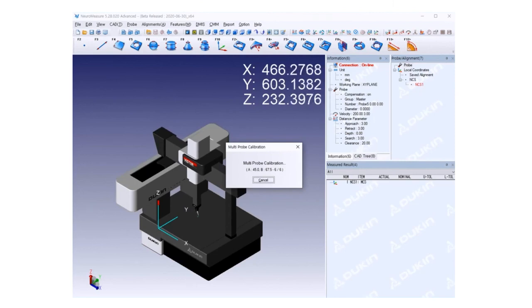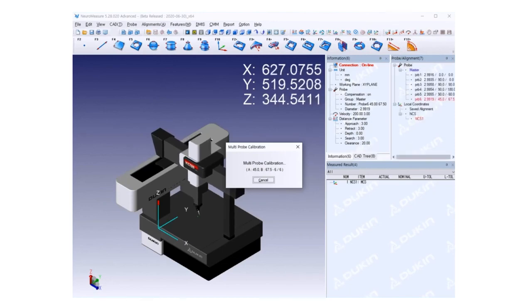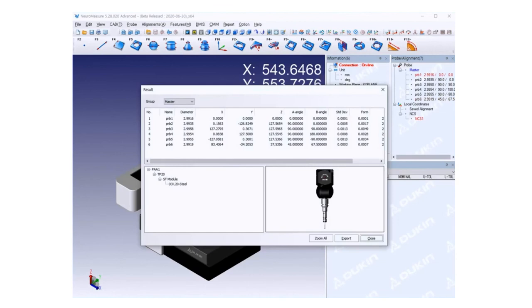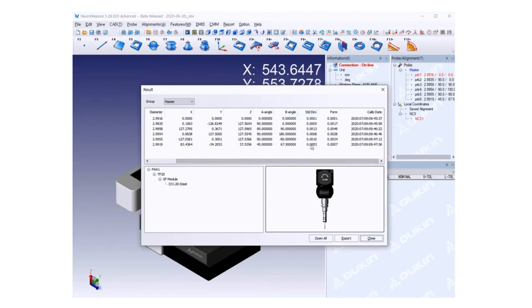So after calibration is done, go back to probe number 1, which is A0 and B0, the reference position, and then the result will pop up. And you can see all these names, calculated actual diameter, and then XYZ as a relative position. You can see that probe number 1 is 0, 0, 0. And then the angles, then the deviation, and then sphericity, which is form. You can see their standard deviation is lower than 3 micrometers, and sphericity is under 5 micrometers.